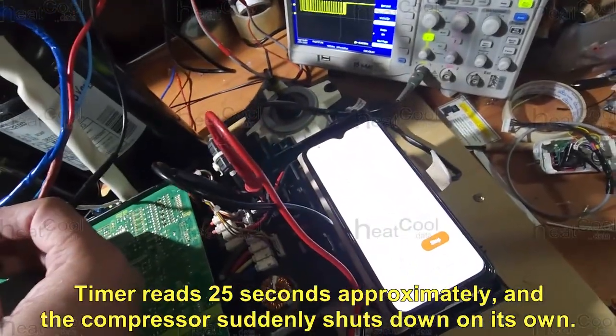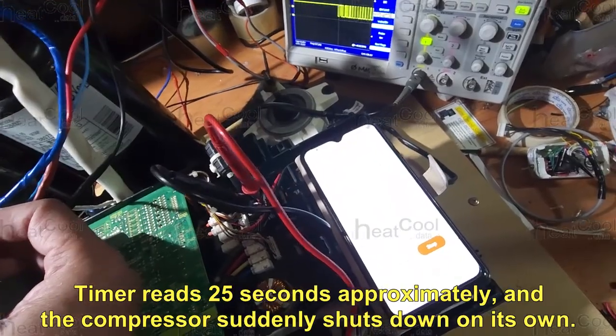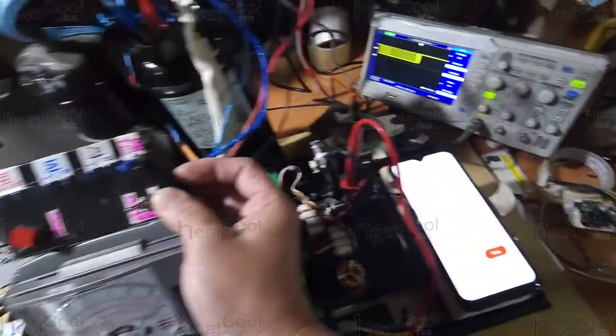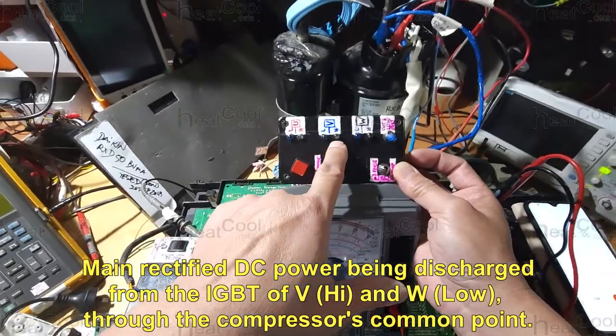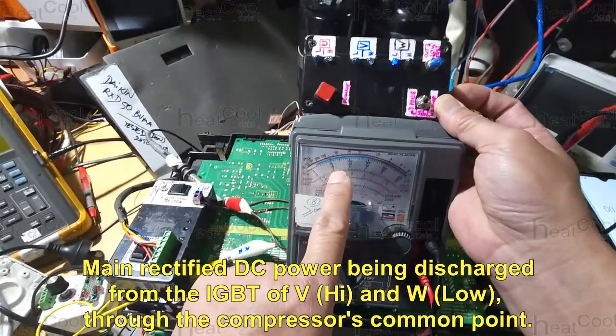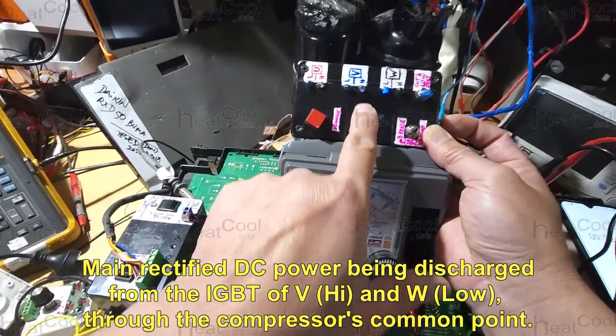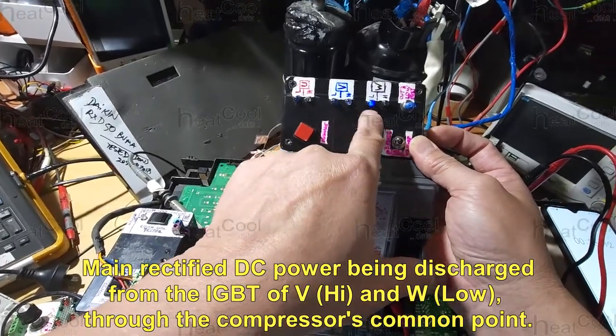Timer reads 25 seconds approximately, and the compressor suddenly shuts down on its own. Main rectified DC power is being discharged from the IGBT of V high and W low through the compressor's center point.